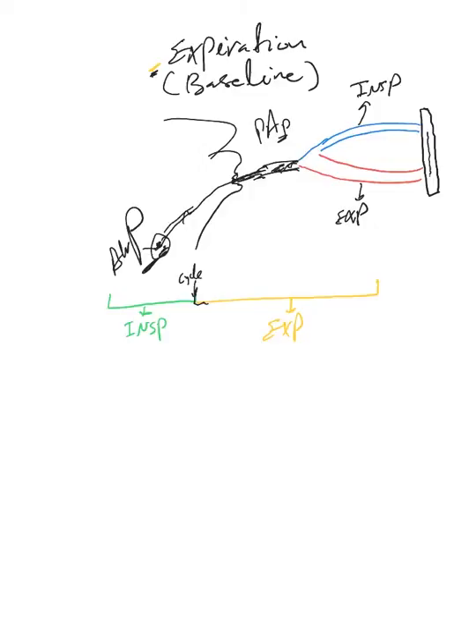Here, which is small. Also, the ventilator—as soon as expiration finishes—will close the valve here and open the expiration valve to allow the air to flow here. Now look here: as you see, the expiration is way longer than inspiration, and usually in healthy adults, the expiration is longer than inspiration.